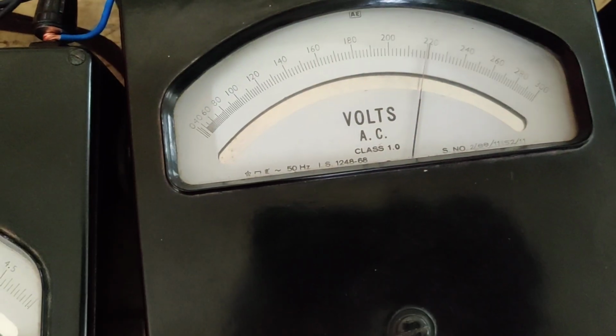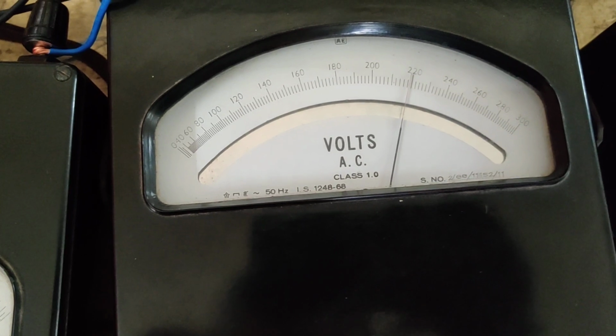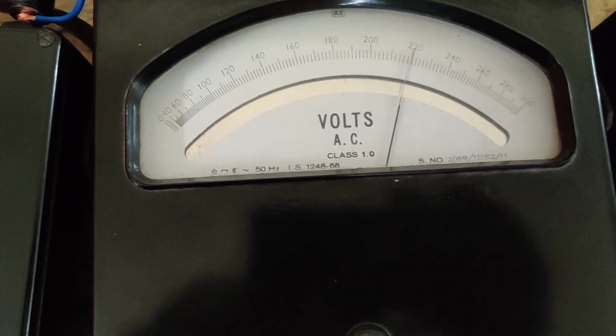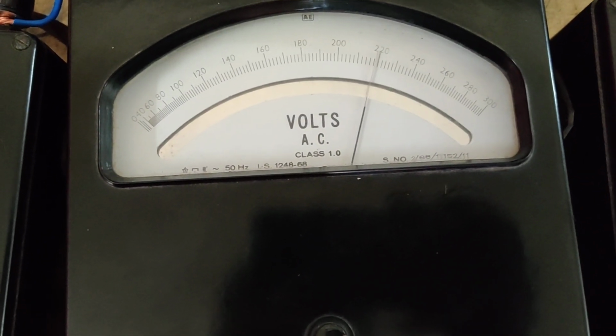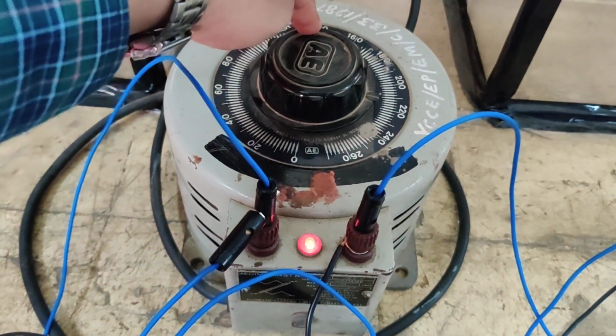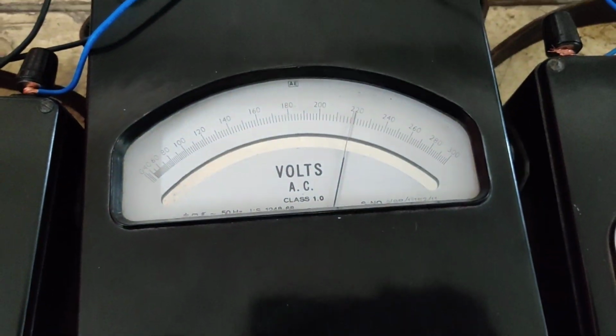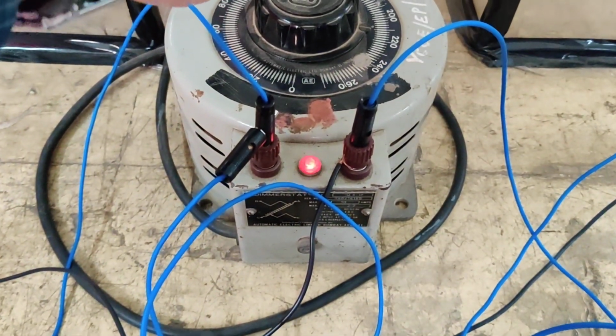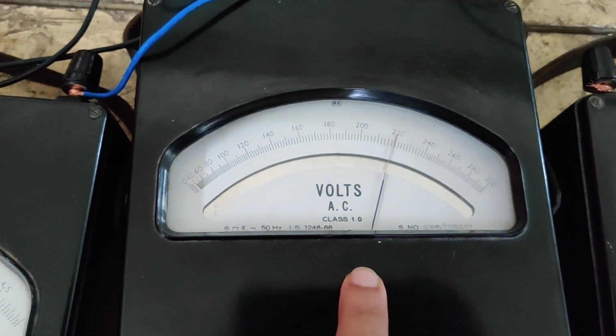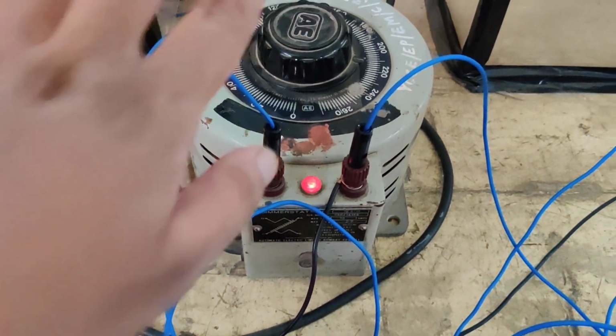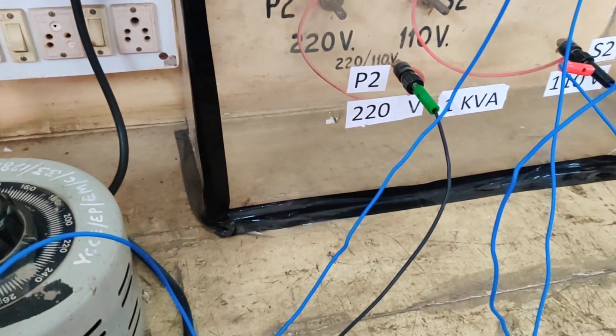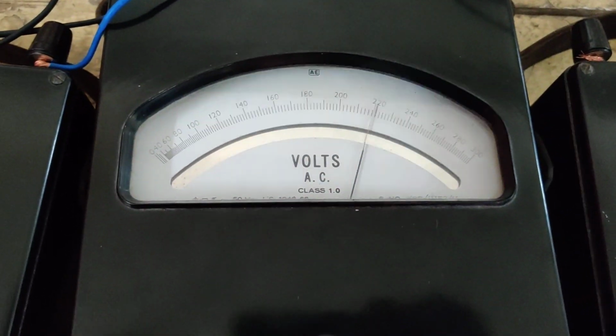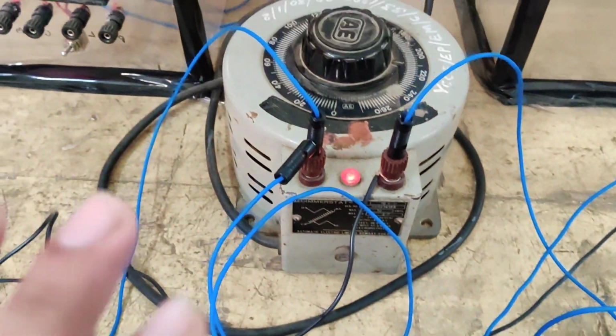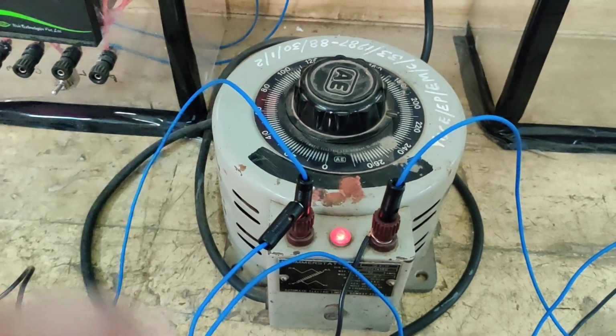But the problem is, when I try to maintain my voltage by adding load, simultaneously my primary voltage will drop down, and I have to maintain this voltage using the variac. But the problem is, when I try to adjust it, by referring to this voltmeter, the variac is supposed to move. Many times we forget to move this, and the initial voltage will rise more than 220 volts. That is why we omit this process and keep it untouched; we are not supposed to touch the variac.